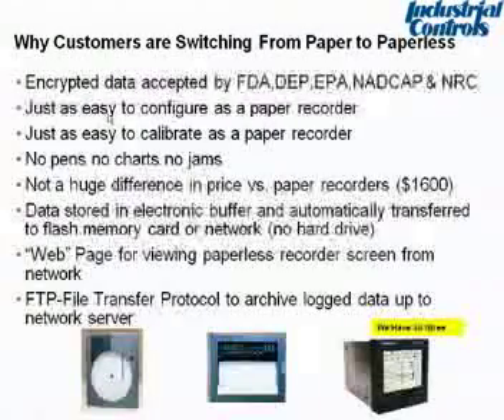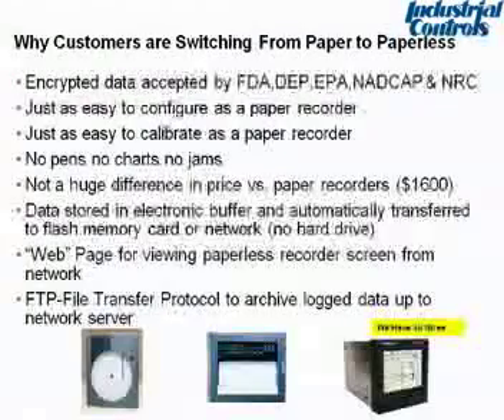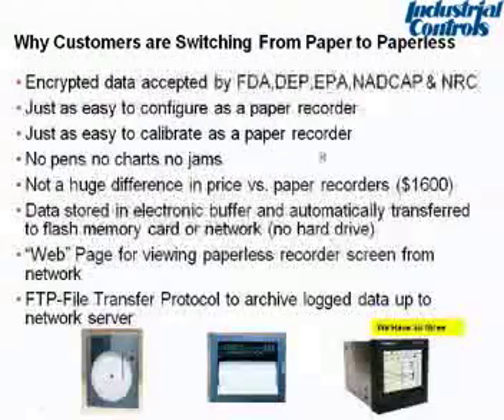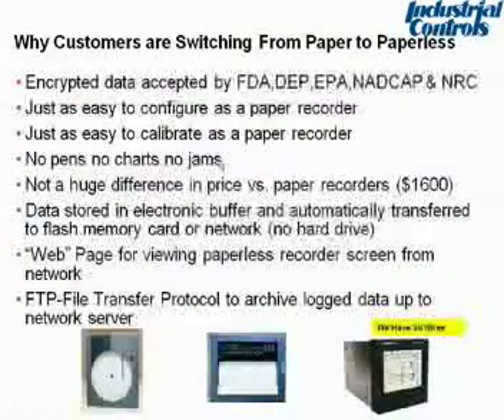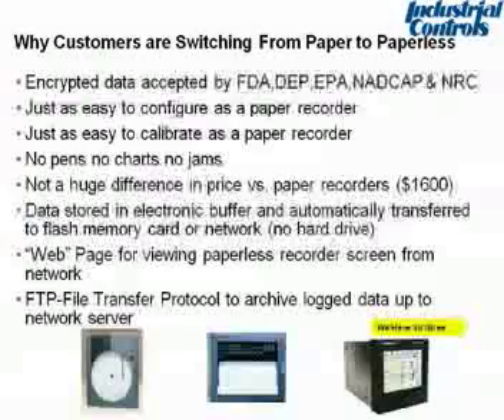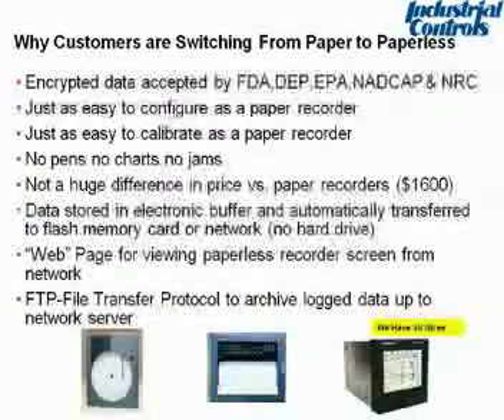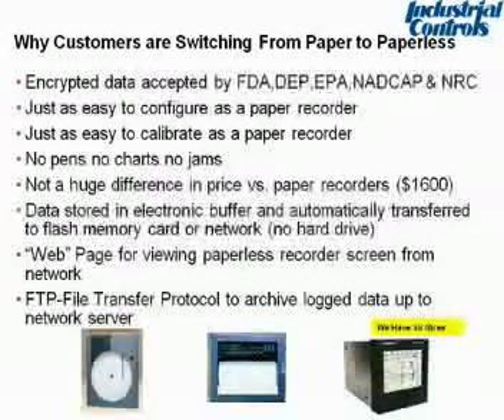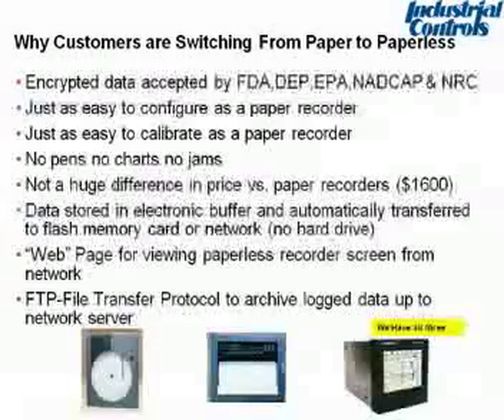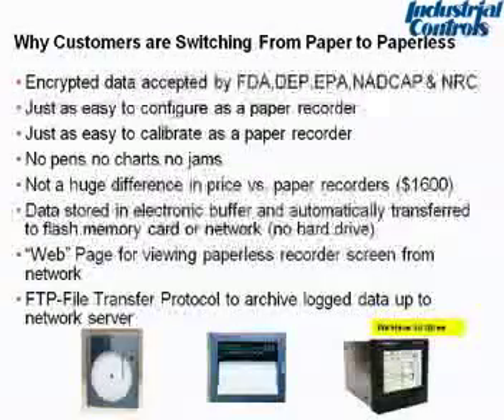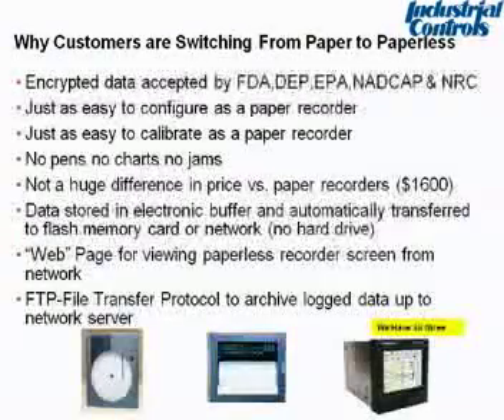You'll find as we go through today that the paperless recorder is just as easy to configure, and in some cases easier, than a paper recorder. Same with calibration—I'll show you the calibration screen that comes up when you check the as-found calibration on your paperless recorder. And of course, no pens, no charts, no jams. There was a time where the FDA, for example, when they came in to give an audit, would see notes in the compliance data indicating a chart was jammed or the pens ran out of ink, and at that time they may or may not give the customer a pass. I'm here to tell you that the feedback I get is that if a chart fails or the pen runs out of ink, there's a 4 to 6 hour report required in order to justify that the parameters were within FDA regulations at the time the chart jammed.